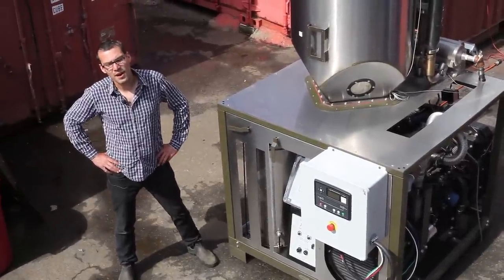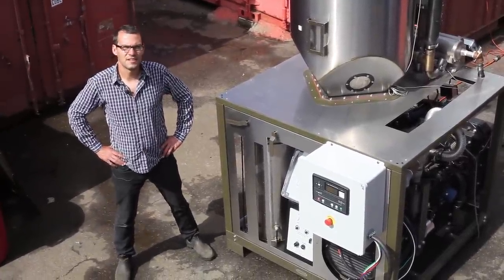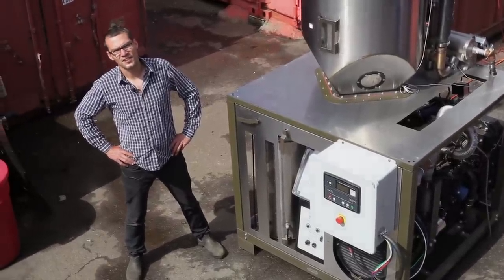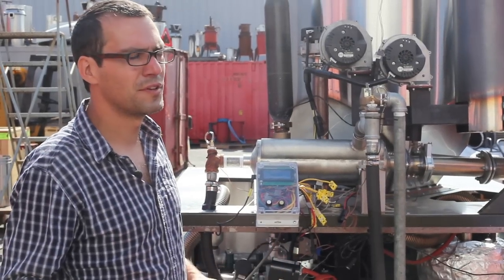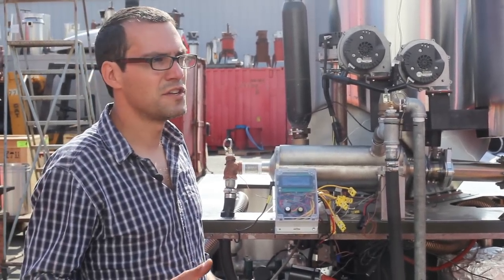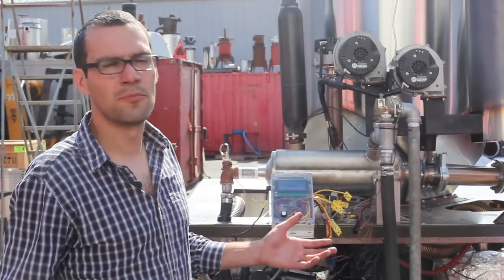The combined heat and power system harnesses the heat created by the engine in the engine coolant water as well as the engine exhaust. This CHP system produces approximately double the amount of energy in heat to the water as it does in electrical output.